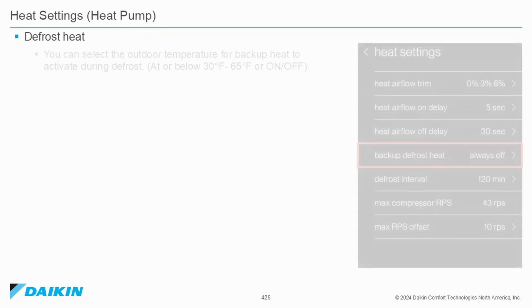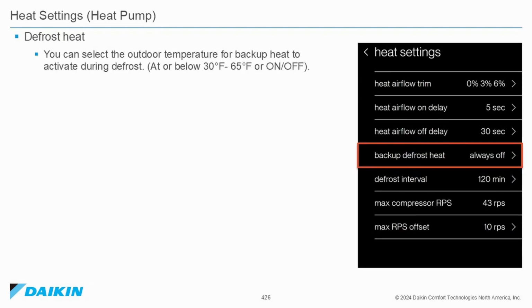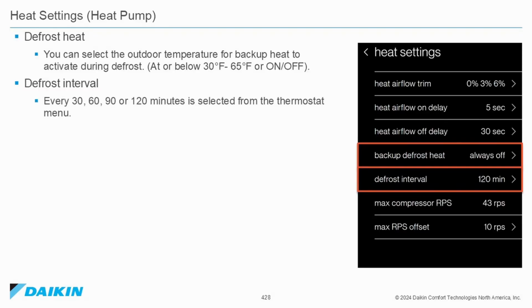Heat settings for the heat pump. Defrost heat. You can select the outdoor temperature for backup heat to activate during defrost, at or below 30 degrees Fahrenheit to 65 degrees Fahrenheit, or on or off. Defrost interval. Every 30, 60, 90, or 120 minutes is selected from the thermostat menu.